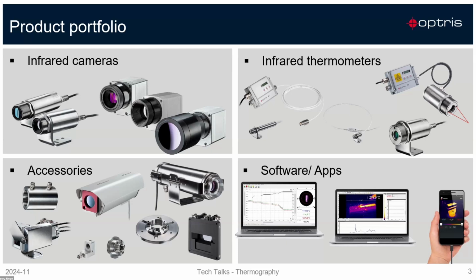We provide small sensor heads with different optics, and also bigger sensor heads with laser diodes, so you can see your spot directly on your material and be sure you're measuring the right position. This group of pyrometers includes 1-color and 2-color ratio pyrometers. These pyrometers are also available with digital interfaces, nowadays including Ethernet IP, Profinet, Ethernet TCP/IP, Modbus Ethernet, and serial communication.